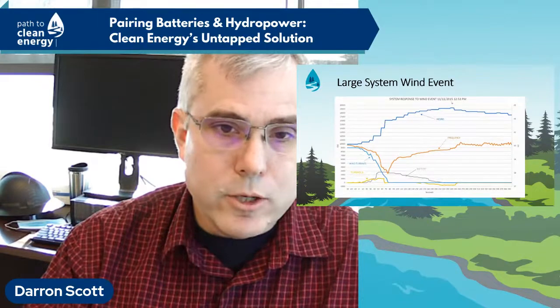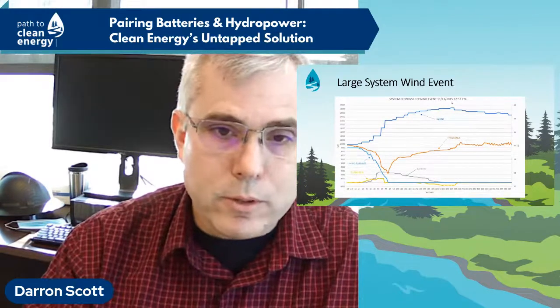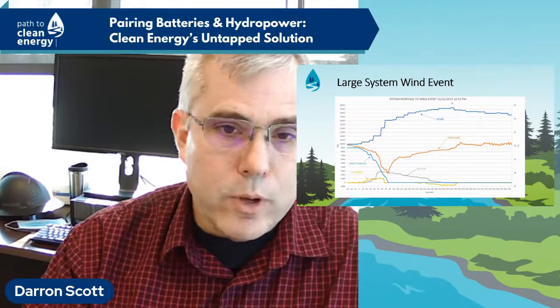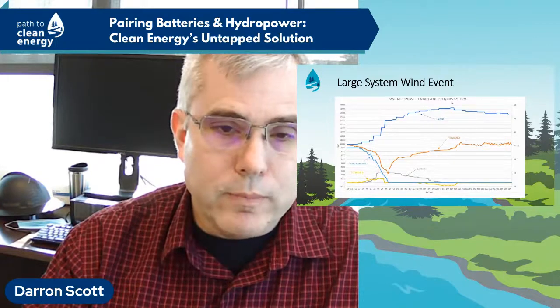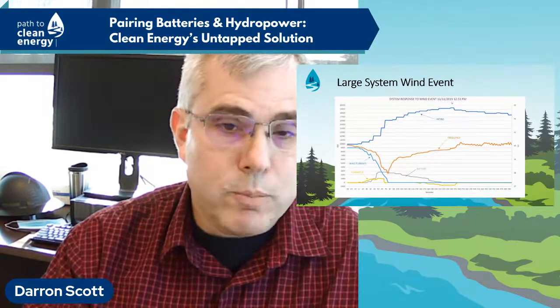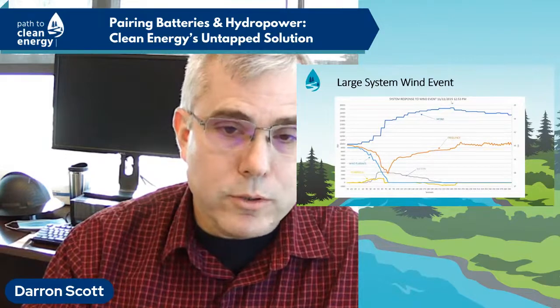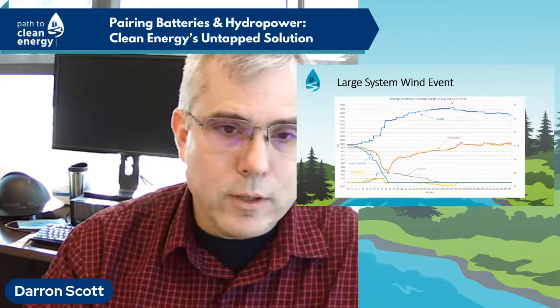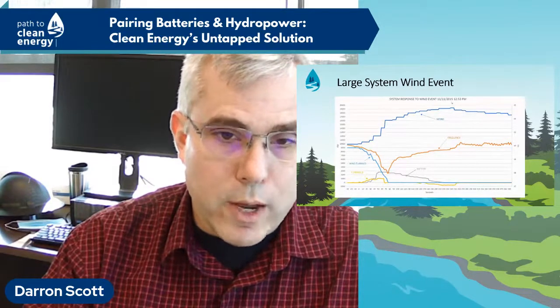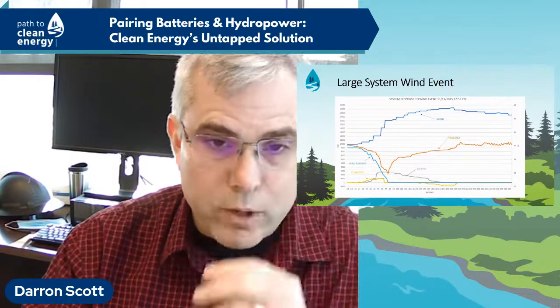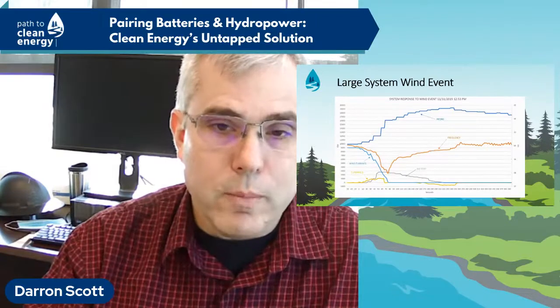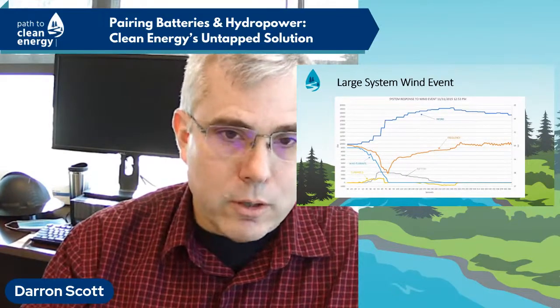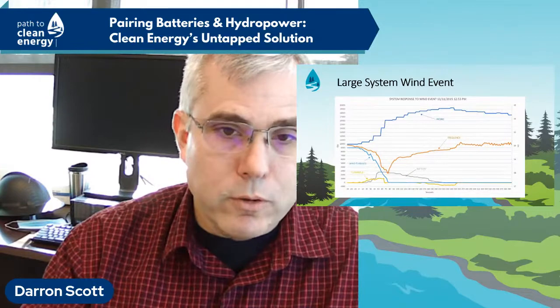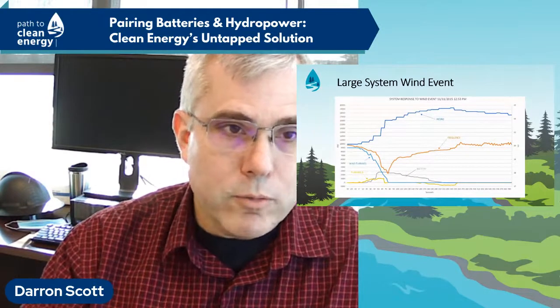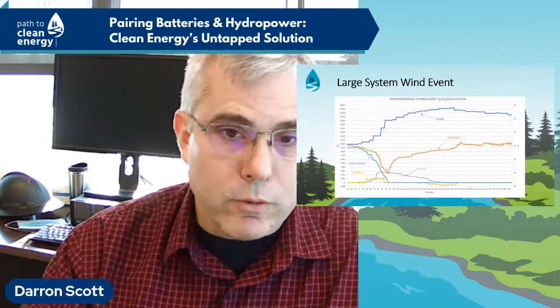As wind can do sometimes, and it's great we're able to capture this data here, wind went over a period of 60 seconds or so from supplying almost half of our energy in our system down to nothing. It's not like the wind system tripped; the wind power just went down to nothing. The wind speeds dropped off for whatever meteorological reason at the time. Now, as you can imagine on a large electrical grid, if you lose almost 50% of your generating capacity, your frequency is going to suffer.